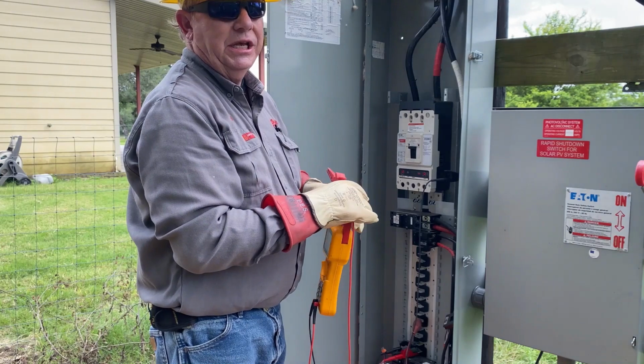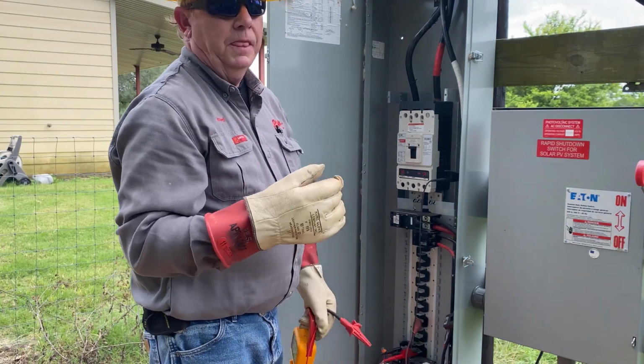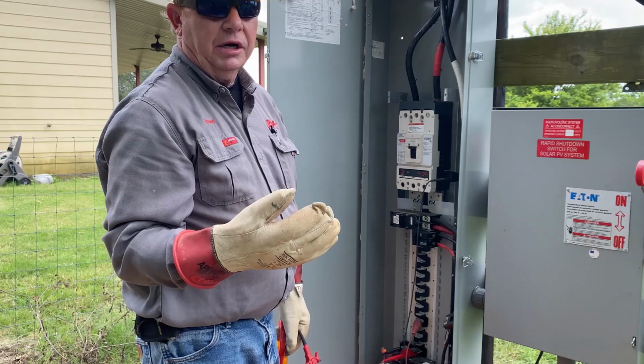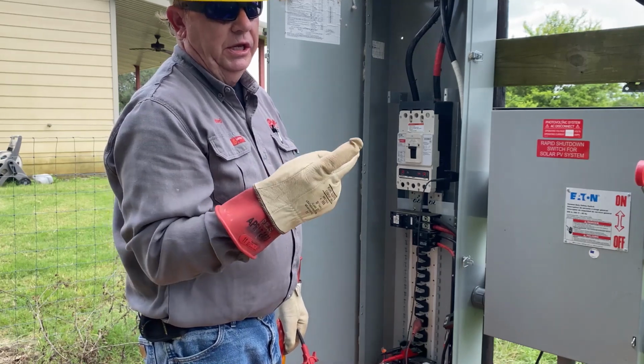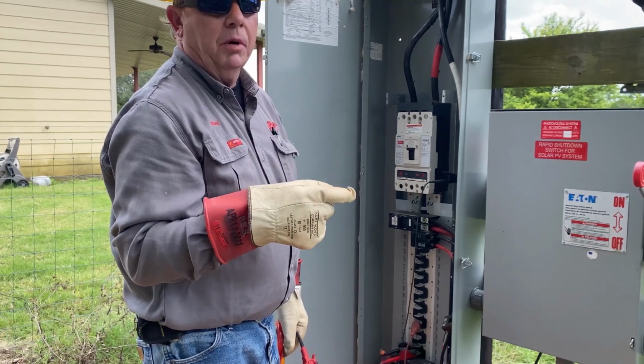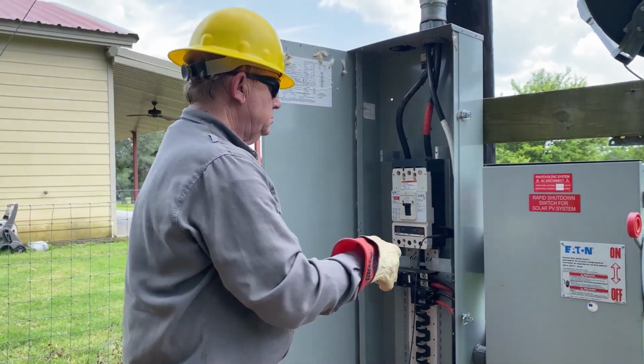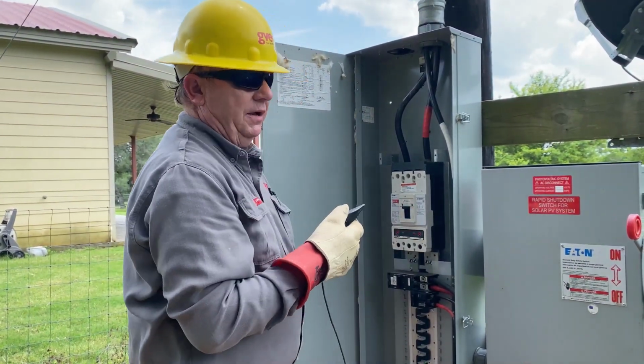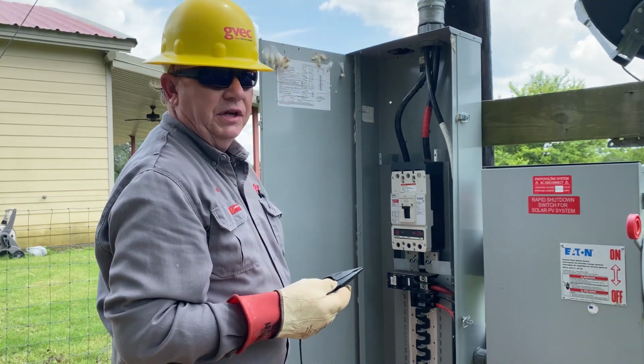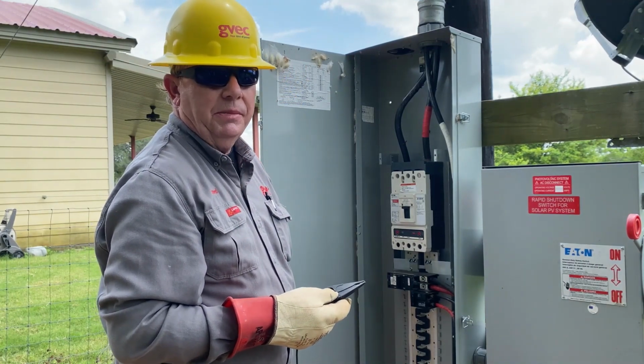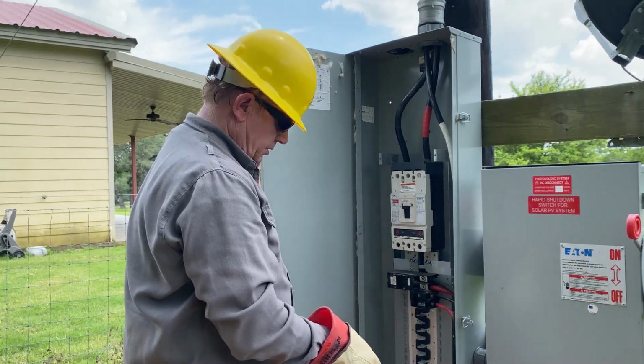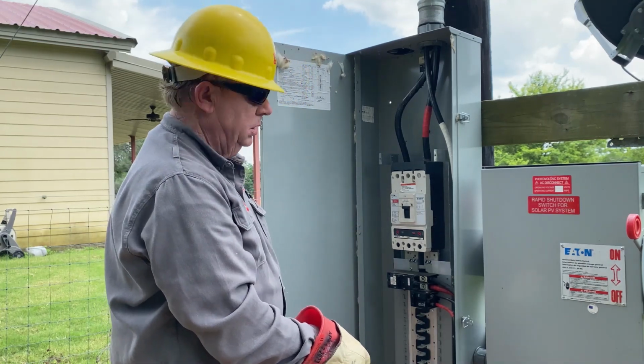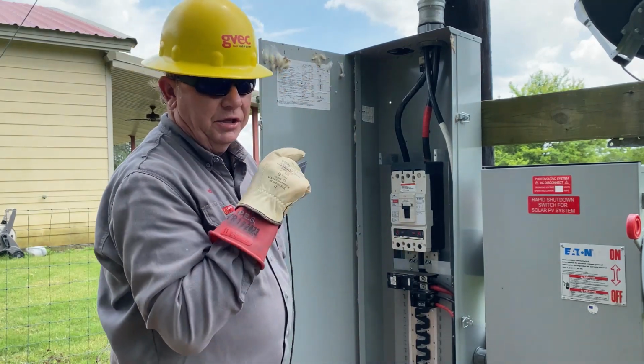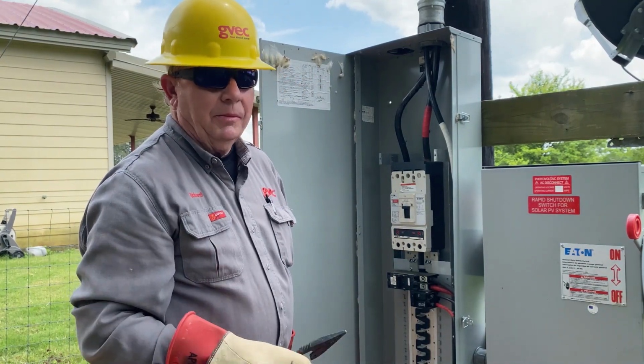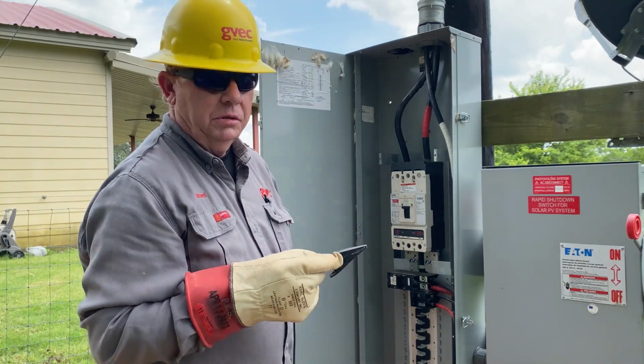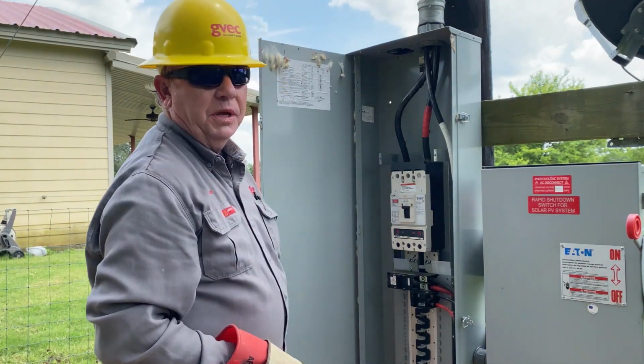These flickers that he sees may be coincidental with these air conditioner and dryer. A dryer does have a 120 volt load. The heaters in a dryer are 240, but the tumble motor is 120. And since I can see the back of this looks like a 750 lug is scorched against the sheet metal, there's a ton of resistance between that bonded neutral bar and this lug headed back to the transformer. Right now I'm going to blame all of the symptoms on the way that this riser has been built.